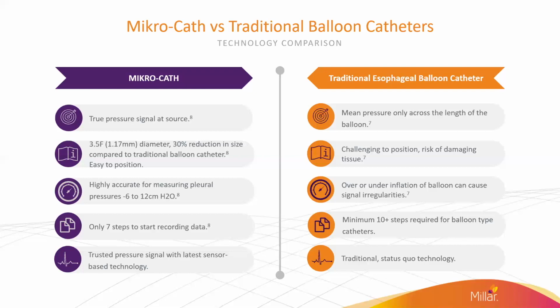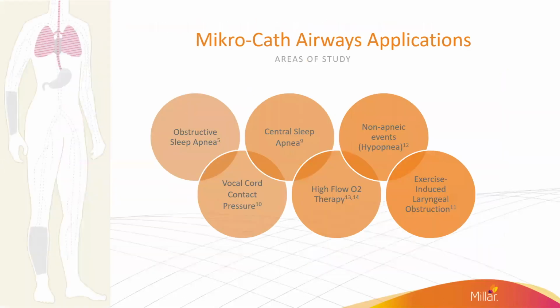As the Mikro-Cath does not require any form of inflation, setup, positioning, and signal recording can be achieved in 7 quick steps. Once the Mikro-Cath is placed, it can be left in situ for up to 24 hours with no requirement for readjustment, which is often not the case with balloon-type catheters. The Mikro-Cath excels at measuring small pressure changes. Because of its sensor design, the Mikro-Cath is used in a wide variety of applications.